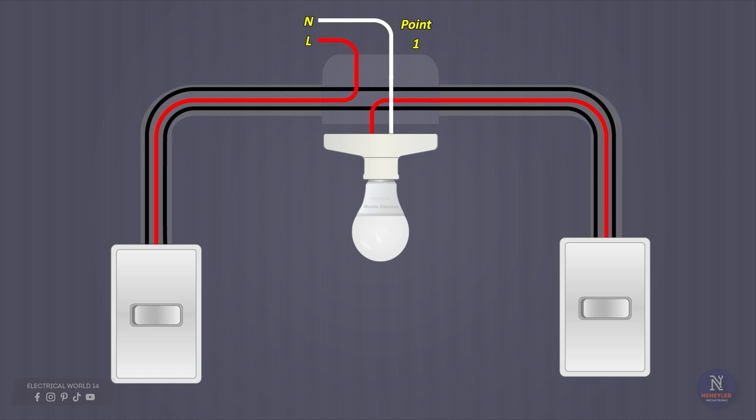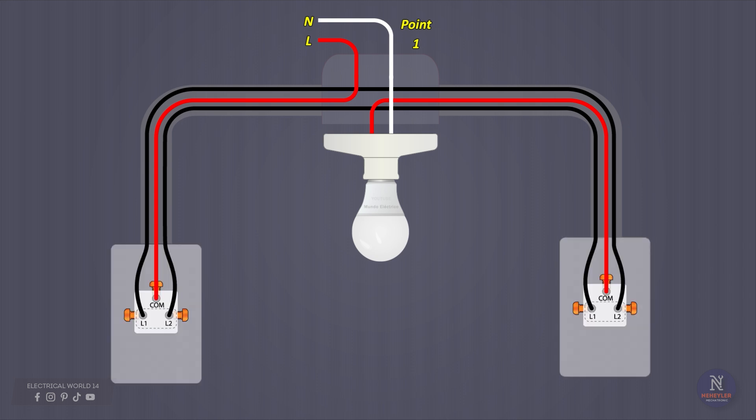If in this case it stays on and does not turn off, it is because something has been connected wrong in the switches, but don't worry. As long as you do not connect the phase and the neutral, there will be no short circuit. Just de-energize the cables and correct the error by changing the position of the cables between the switch terminals.